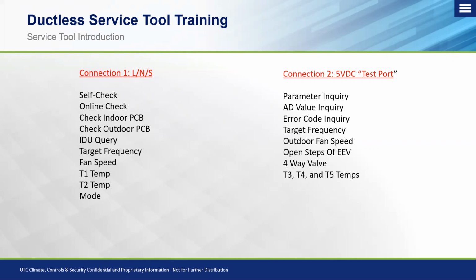Okay, so depending on how you want to wire in, it is going to give you different data. Typically, what I tell guys is, if they're looking for a rule to split up which connection you want to use: if you're trying to test individual components of the outdoor unit, I suggest that you use the 5-volt DC test port plugin, because there you can get in and fire off individual components such as the compressor, the 4-way valve, the EXV, and verify that they respond properly from the signal sent from the tool.